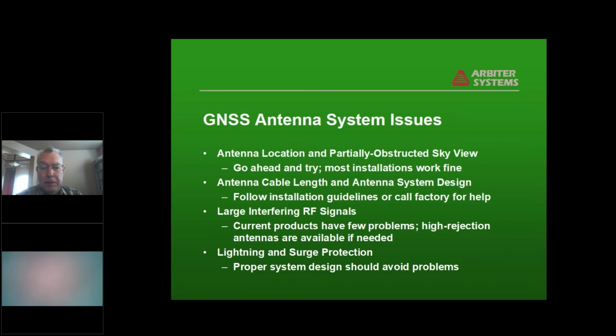Newer products are much better at that than the old original GPS receivers were. And we offer, and I think most other companies offer, high rejection antennas for areas where they're needed, but we see less and less of those problems even with standard antennas. Lightning and surge protection is also an issue in some locations. Florida gets a lot of lightning, for instance, and for almost all GPS clocks installed in areas like that, you have to make sure you provide the type of surge arresters and lightning protection that's required. Our clocks have a fair amount of that built into them.